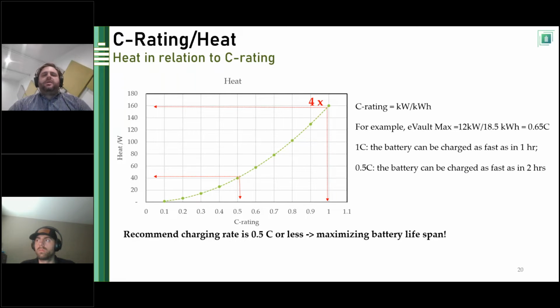And no matter how you cut it, if you have a battery that's rated for a 1C rating and you only run it at a C/2 rating, which is a 2-hour discharge rate instead of a 1-hour discharge rate for a full discharge, the battery that is discharged at the C/2 rating with lithium iron phosphate chemistry will last longer. And so what does that mean with regard to the Sol-Ark?